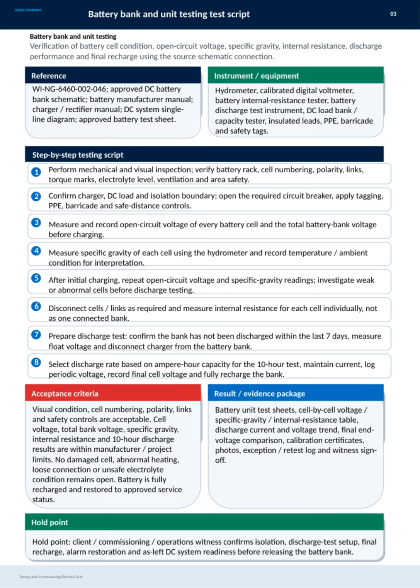It's essential to measure and record the open circuit voltage for each cell and the total bank voltage to establish a baseline. Next, specific gravity readings are taken with a hydrometer, along with ambient conditions, which help assess electrolyte health. After initial charging, these measurements are repeated to spot any weak or abnormal cells, which must be addressed before moving on. We also individually measure the internal resistance of each cell, which offers insight into cell health not visible through voltage or gravity readings alone.